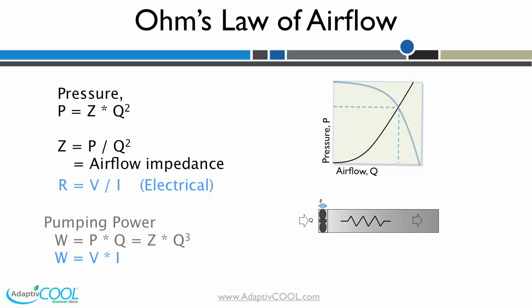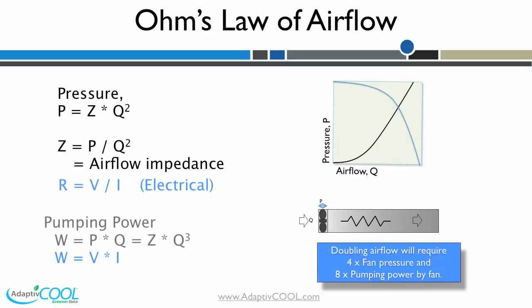By substituting for P, we get pumping power as Z times the cube of airflow. In other words, in a given system, to double the airflow it takes four times the fan pressure or eight times the fan power. These are called the fan laws, and we will use this in the following analysis.